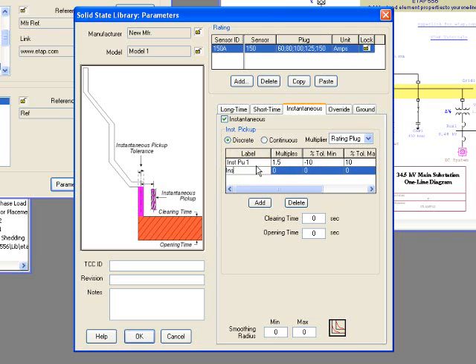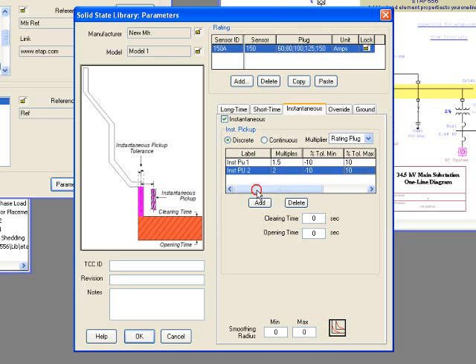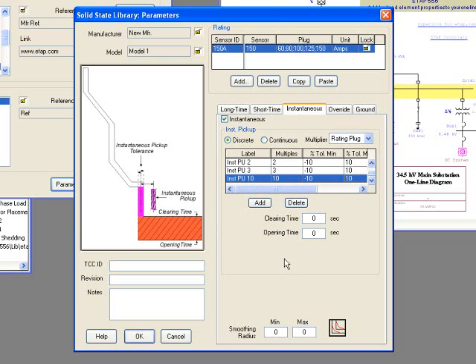You can add as many instantaneous pickups as you want. Keep in mind, instantaneous has a fixed clearing time band, and an opening time band is fixed, not adjustable.